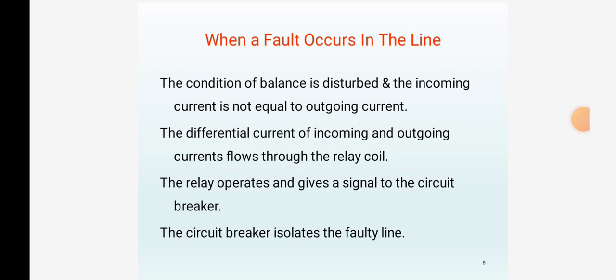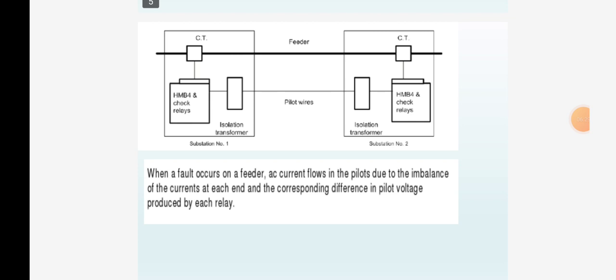In pilot wire protection using circulating current differential relay schemes, the schematic arrangement for the circulating current principle has two CTs connected in each protected line, one at each end. Under healthy or external fault conditions, the secondary currents are equal and circulate in the pilot wires.